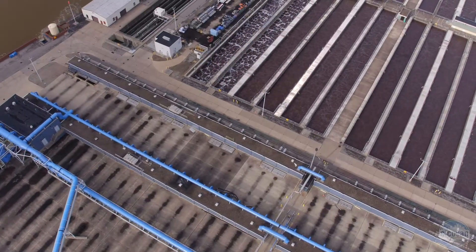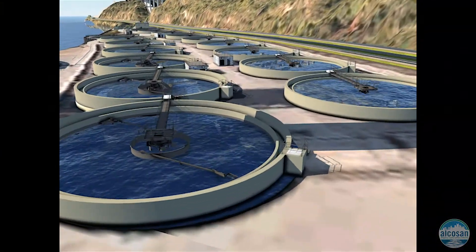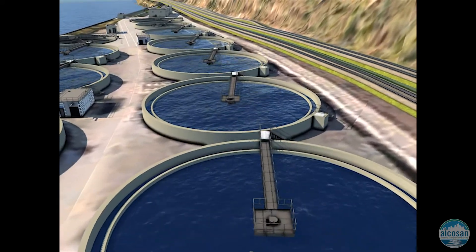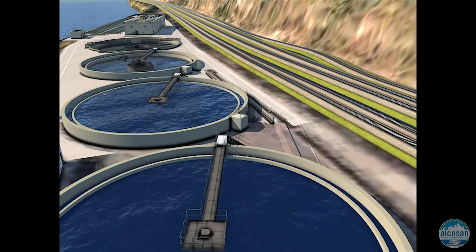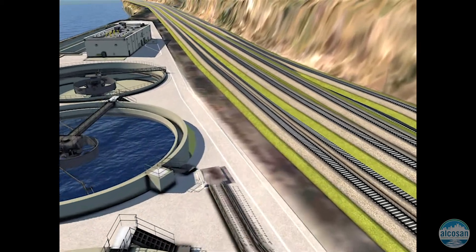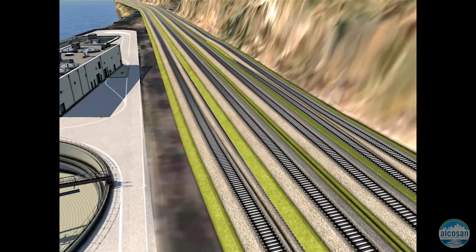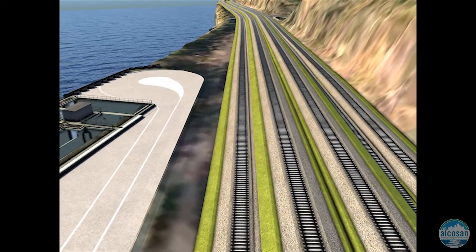Our virtual tour will now continue with our North End plant expansion project. Currently, ALCOSAN treats flows up to 250 million gallons per day. The North End project will increase our secondary treatment capacity up to 295 million gallons per day. Secondary treatment begins at our eight aeration tanks in the central part of our plant and continues north at our 16 circular final clarifiers. One aspect of the North End project will be to construct two additional final clarifiers to bring our total to 18, to treat the increased flows required under the modified consent decree.